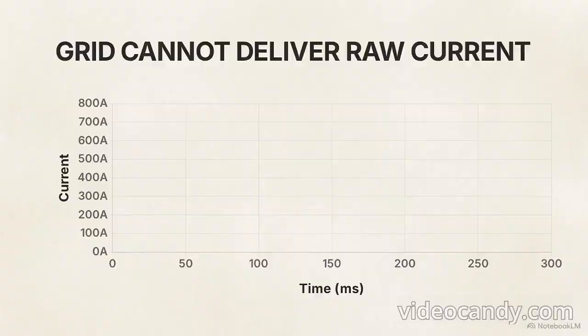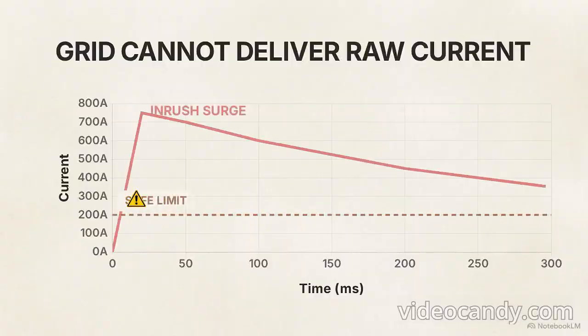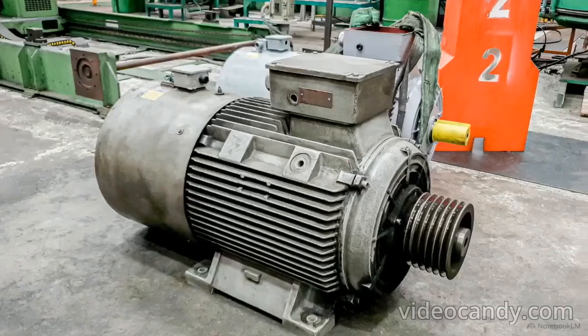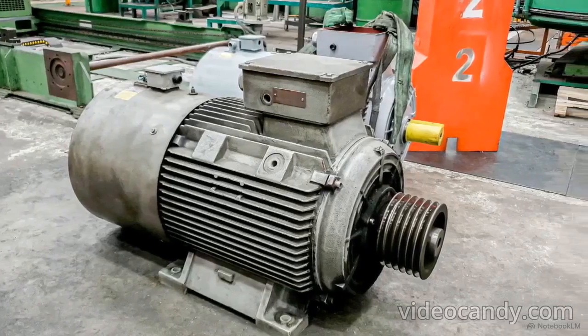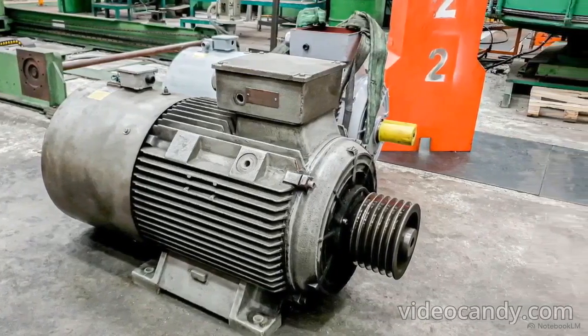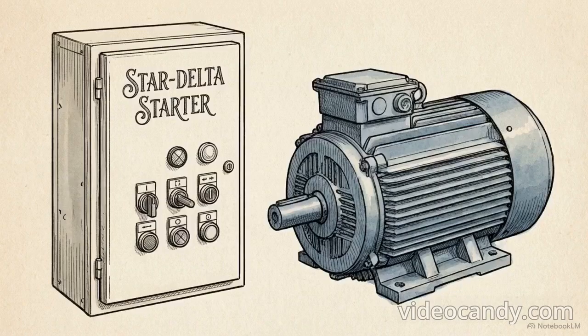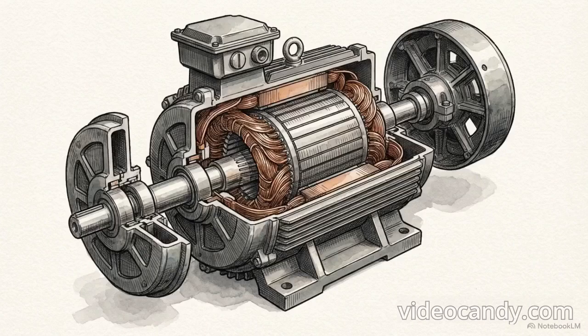The motor needs massive torque to break static friction, but the grid cannot safely deliver that raw current instantly. Large induction motors, generally anything over 5 horsepower, cannot be brute-forced into motion. They require an external starting mechanism to throttle that initial inrush current without compromising the motor's long-term mechanical performance.